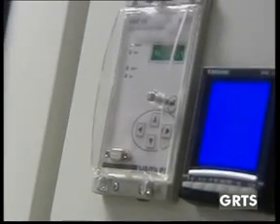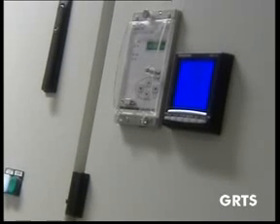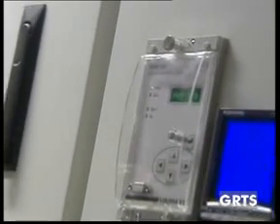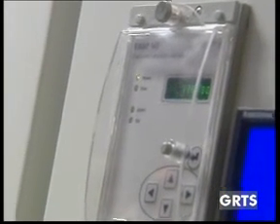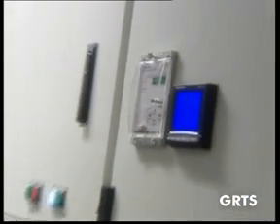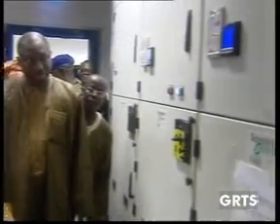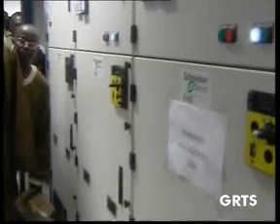You're saying overcurrent and earth fault. Really? What does it mean? What is it telling us? It's a message, because now the engine is not loaded. The engine is not loaded, so obviously you have this. When it runs without loading for quite some time, it triggers an alarm, and afterwards it even shuts down on reverse power.